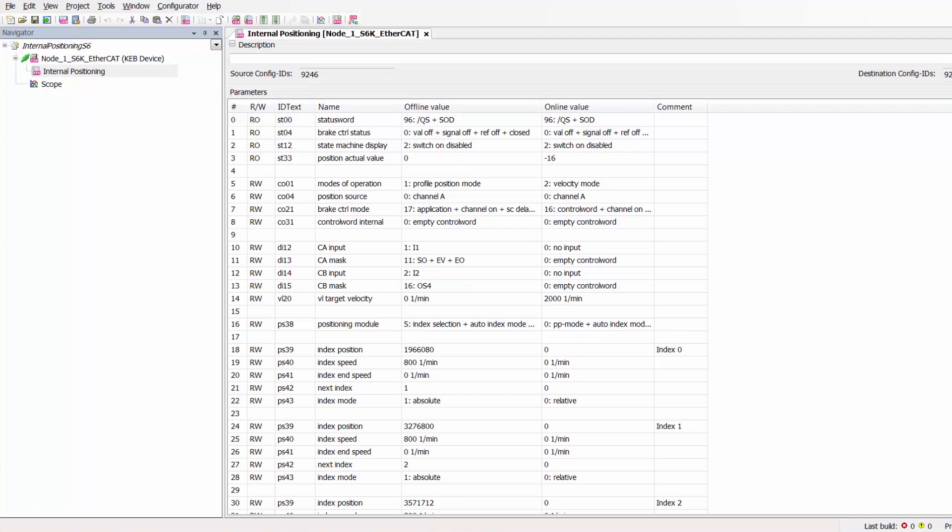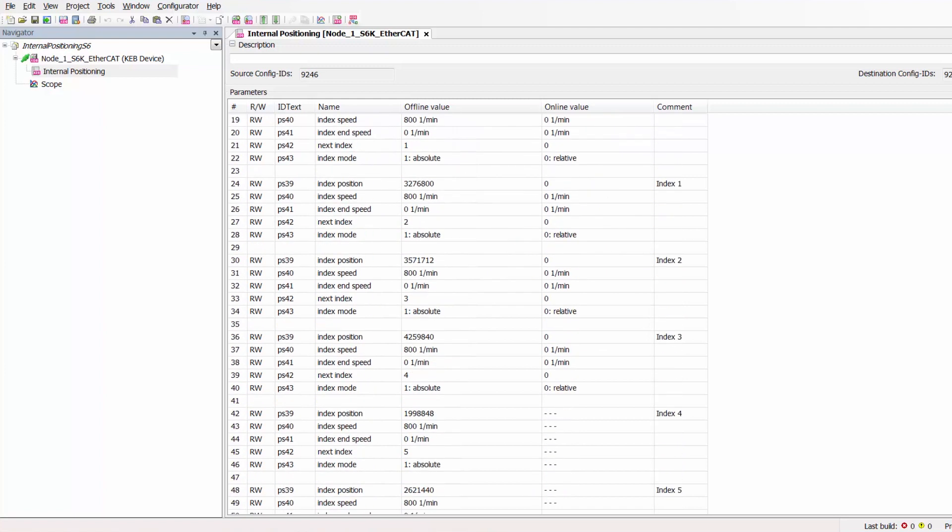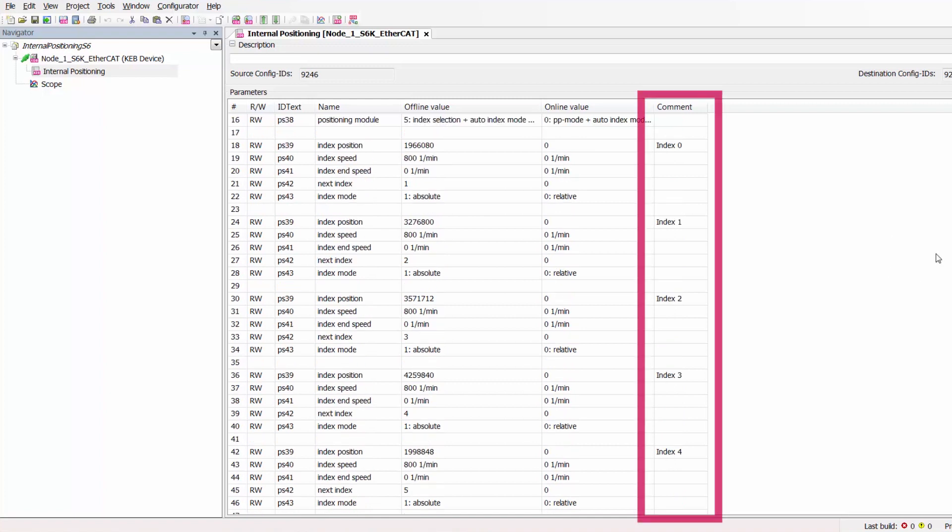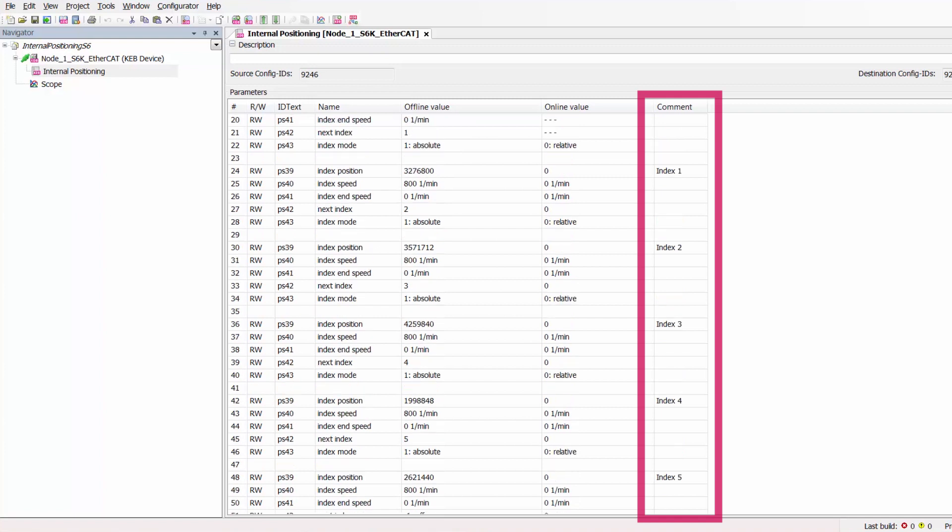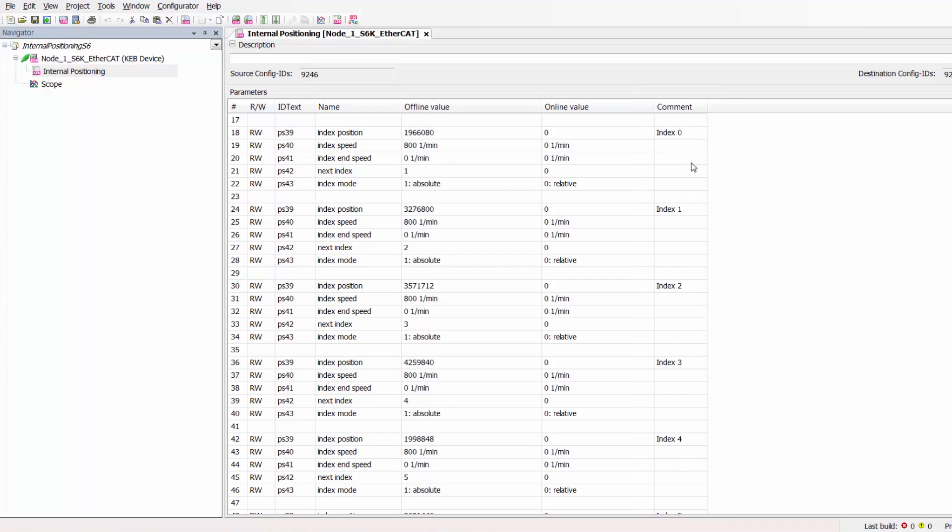So if we scroll down the bottom half of this parameter list actually represents the programmed indexing positions. As you can see here in the comments section I have indicated index 0 through index 5, so 0 through 5 that makes for six indexing positions. As we've stated previously in this video there are up to 32 programmable indexing positions in the S6 drive but just for this testing purpose we are going to only use six positions just for simplicity sake. So each of these indices are just copies of one another but we can just kind of break apart what each of these entails in programming each of these indices.